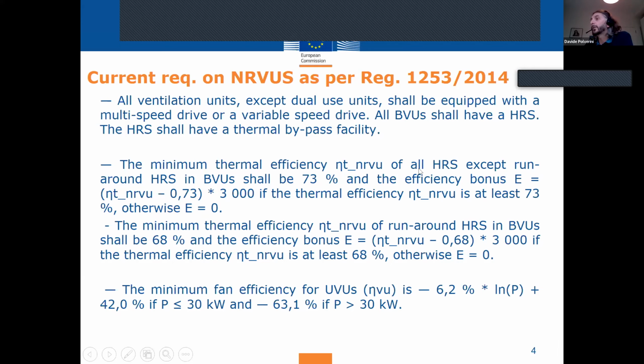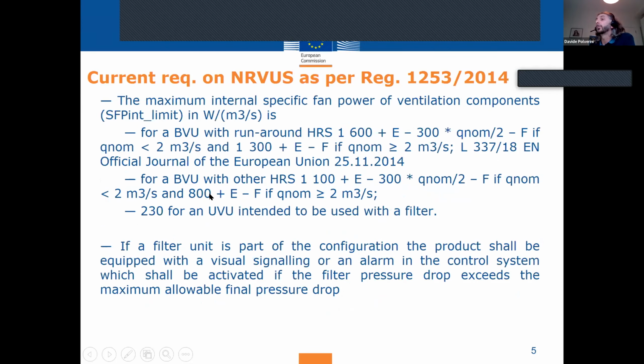For these, at the next point, and this is the main item of discussion, we regulate the minimum value of the thermal efficiency, which is basically an absolute value, which you see here differentiated on the typology of ventilation units. There are also other requirements, in particular those related to the maximum value of the internal specific fan power, and the need of a visual signaling or alarm related to the filter unit. So these are the current requirements already in place for non-residential ventilation units and their environmental impacts as per this regulation.